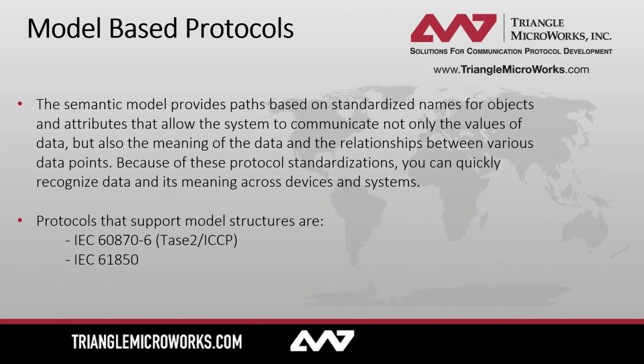Model-based protocol is a little bit different. The semantic model provides paths based on standardized names for objects and attributes that allows for the system to communicate not only the values of the data, but also the meaning of the data and the relationships between various other data points. Because of these protocol standardizations, you can quickly recognize data and its meaning across devices and systems. Protocols that support model structures are IEC 60870-6, otherwise known as TASE.2 or ICCP, and IEC 61850.